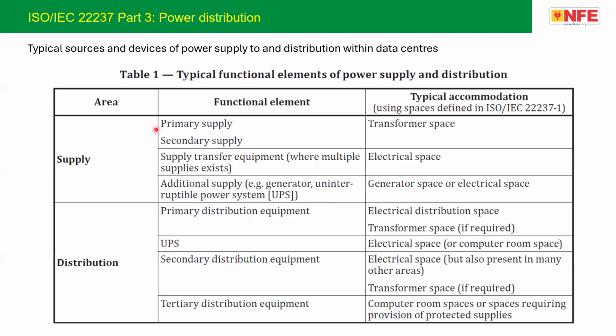Now, going ahead, this particular table 1 in the 22237 part 3 explains you typical functional elements of power supply and distribution. So it's classified as power supply and power distribution. Power supply consists of primary supply, secondary supply, the transfer of the supplies and additional supplies if required. Distribution consists of primary distribution, UPS, secondary distribution, tertiary distribution, and so on. So all these details, for example, the space requirements, are defined in one of the standards.